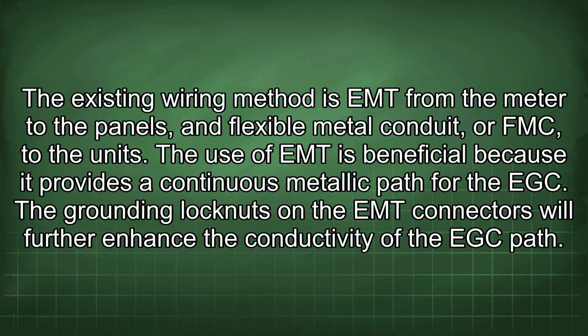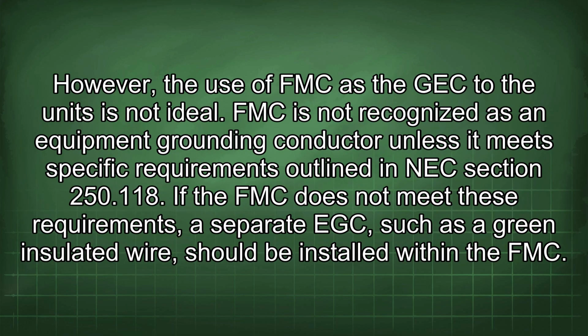The existing wiring method is EMT from the meter to the panels and flexible metal conduit, or FMC, to the units. The use of EMT is beneficial because it provides a continuous metallic path for the EGC. The grounding lock nuts on the EMT connectors will further enhance the conductivity of the EGC path. However, the use of FMC as the EGC to the units is not ideal. FMC is not recognized as an equipment grounding conductor unless it meets specific requirements outlined in NEC Section 250.118.